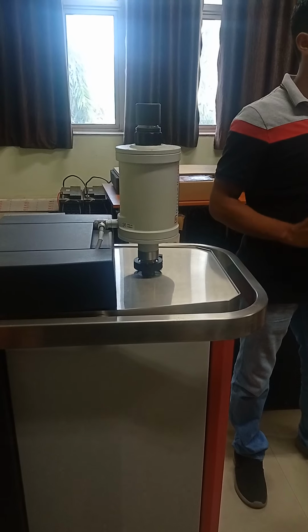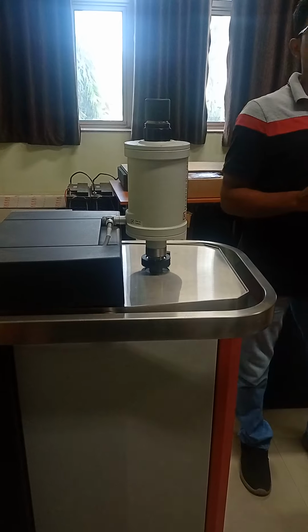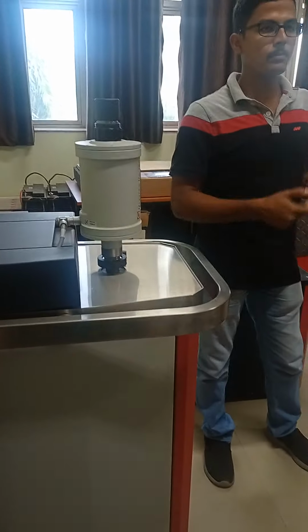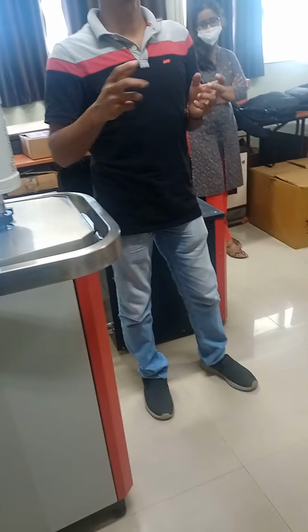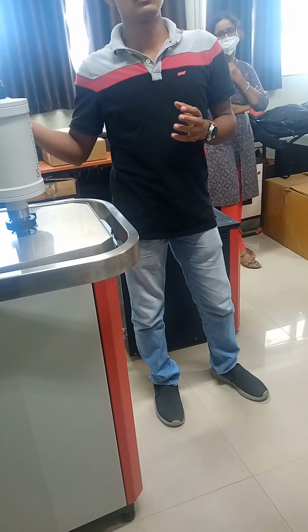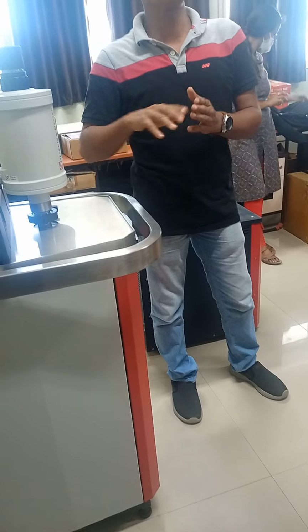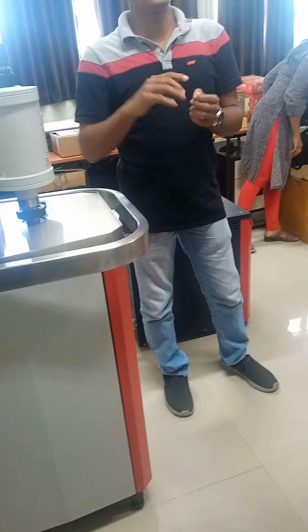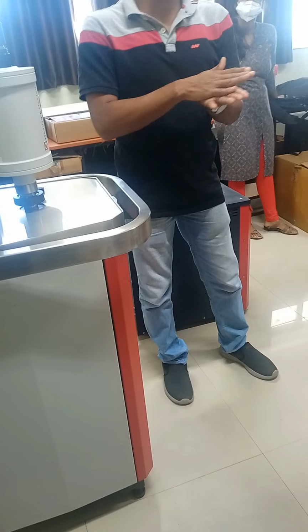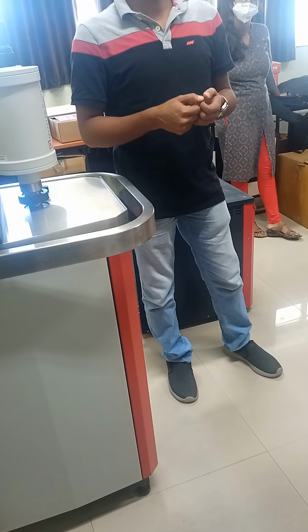So therefore, there are 4 pickup coils. What is the function of those pickup coils? When the magnetic flux changes, that change in magnetic flux is instantly collected by the pickup coil and transferred to the electronic system, which converts this change in magnetic flux using a reference sample by which it is standardized. By comparison with that standardized sample, it will calibrate how much magnetic moment is within the material.